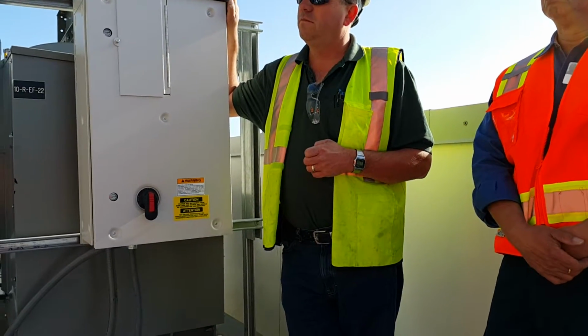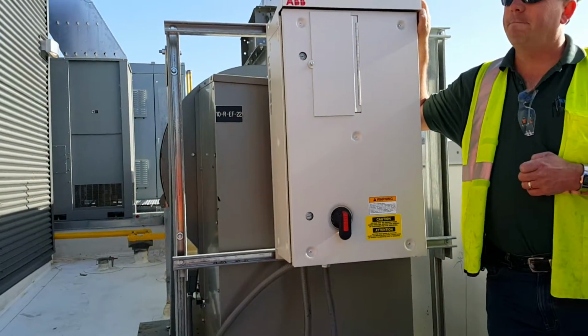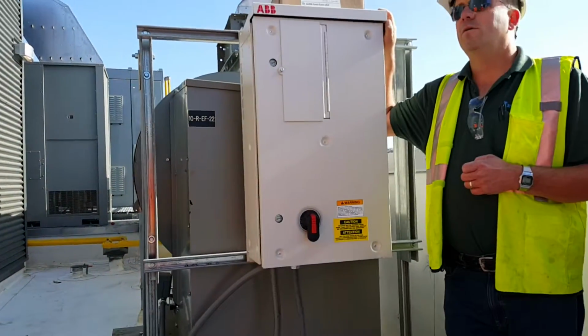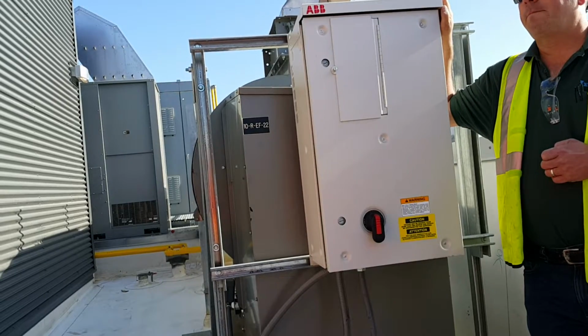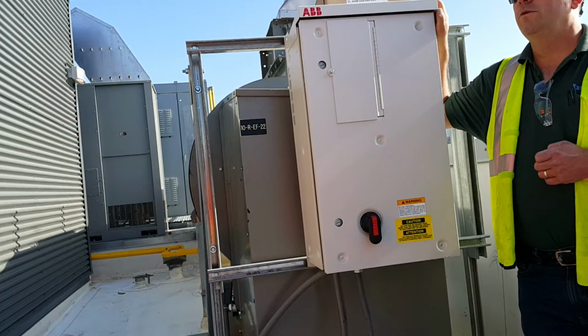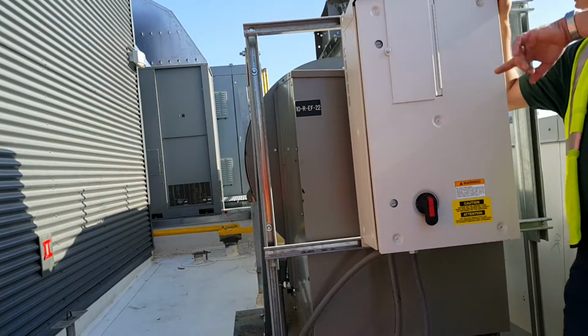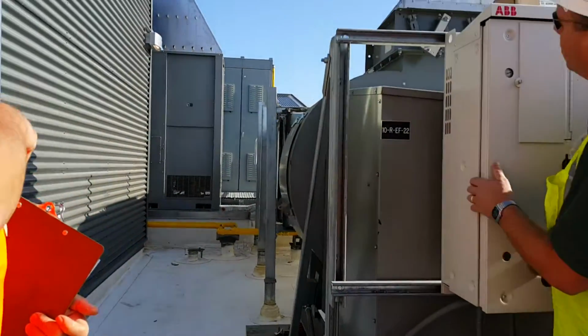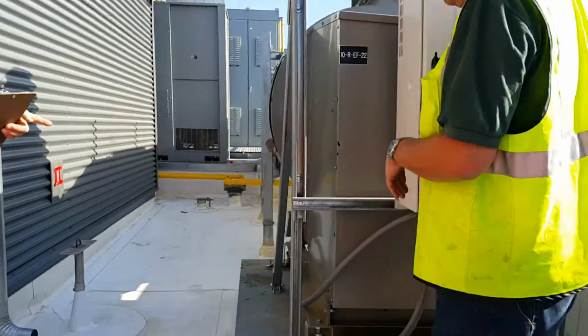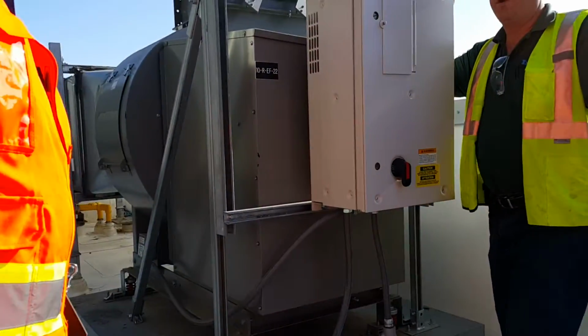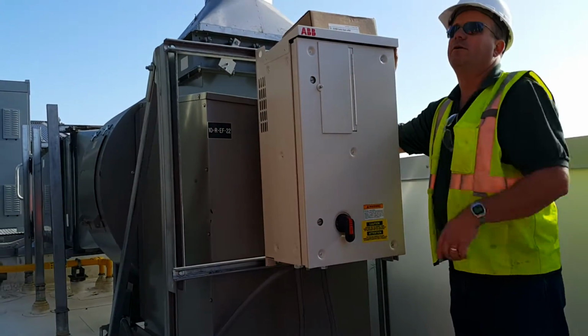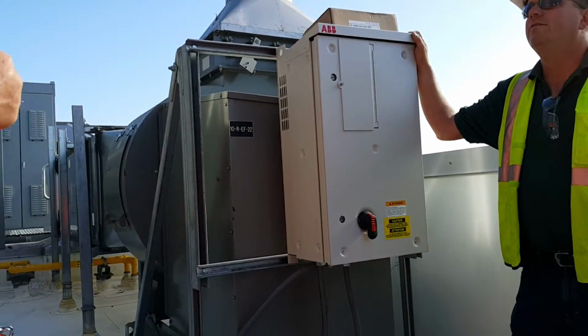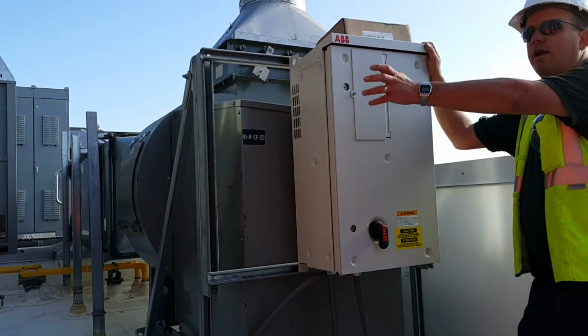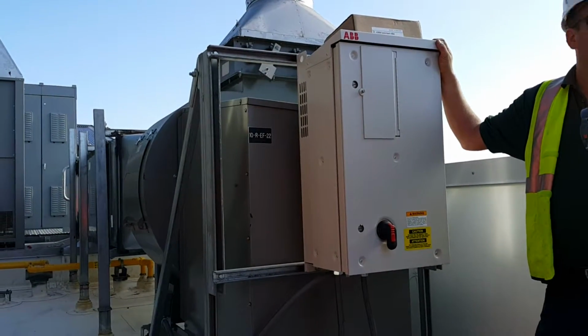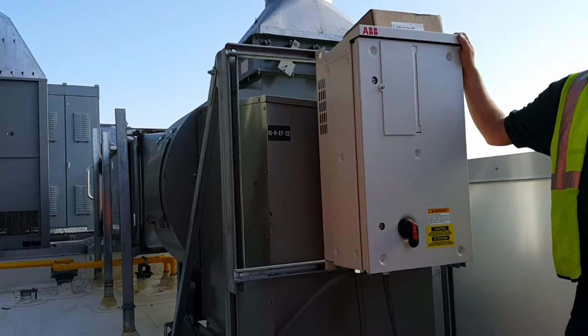Now, are these drives on separate power supplies from the motors, or do you have a disconnect at the panel, and then a local disconnect at the motor? Is the drive on the panel disconnect, or is it a separate power supply? Generally, this one doesn't have it, because you're so close. But there's cases where there's a disconnect over there. Yeah, there's a local disconnect. So it'll come from the breaker panel to here, then here to the disconnect to the motor. So basically, the drives are on the same circuit as the motor. Yes. Every drive has a dedicated circuit from the main panel, and then from the drive to the motor.